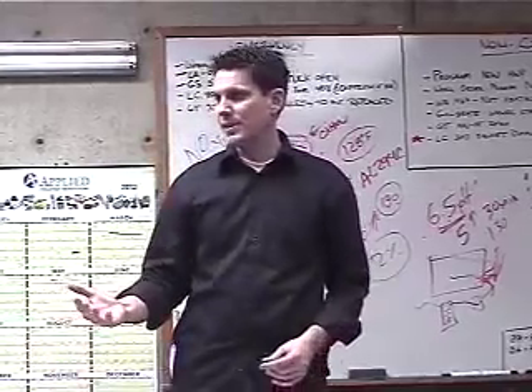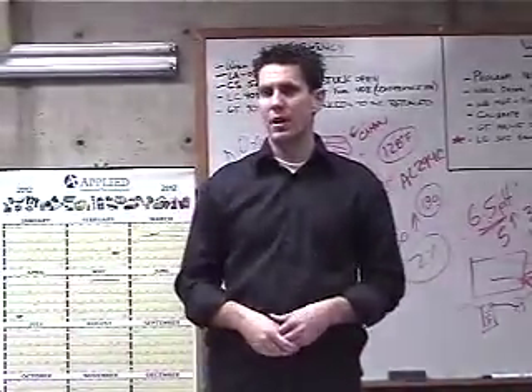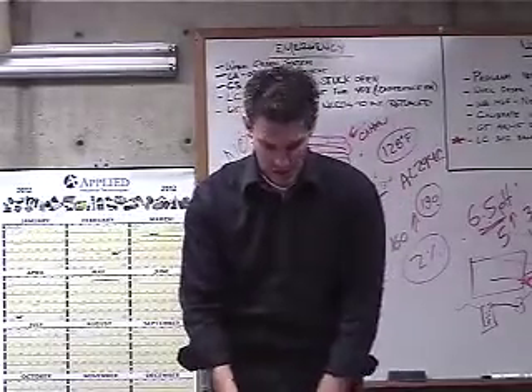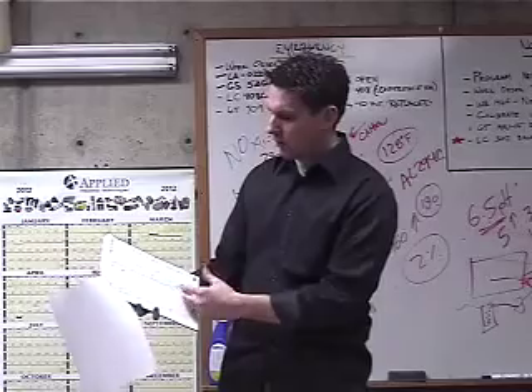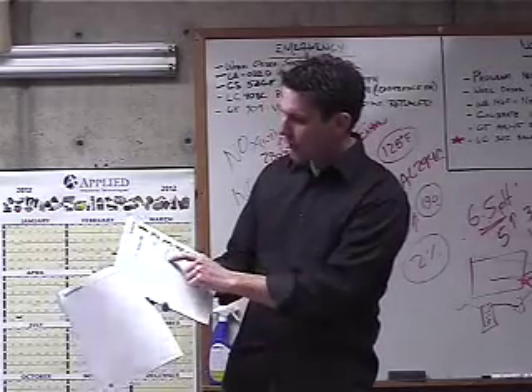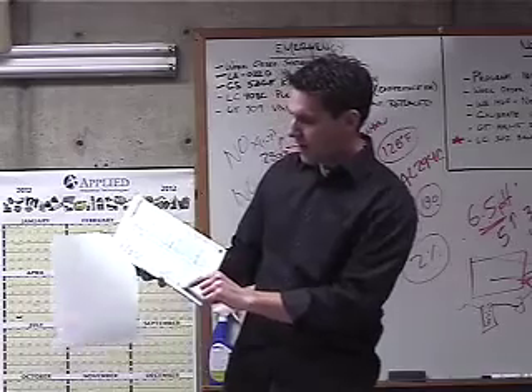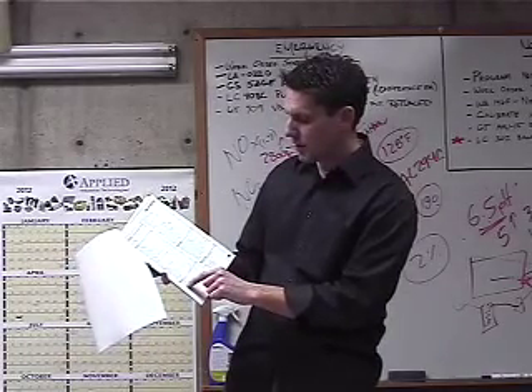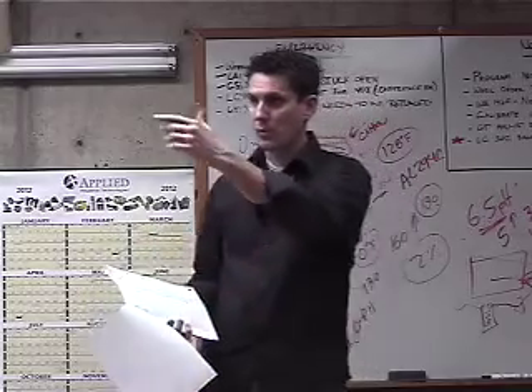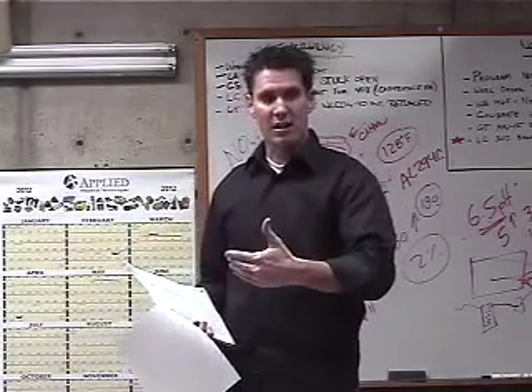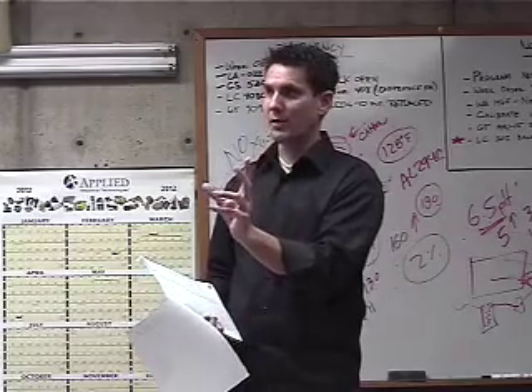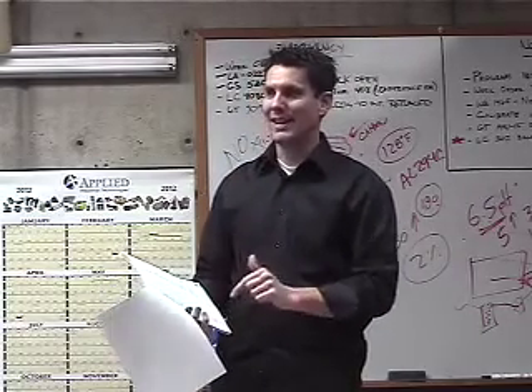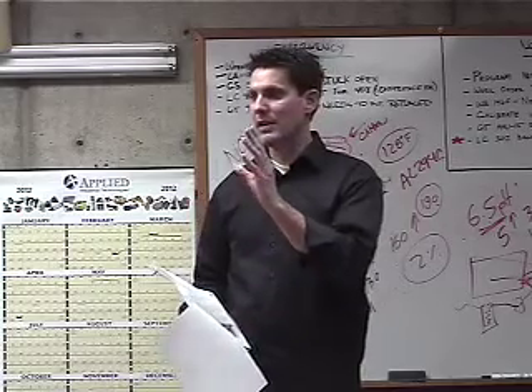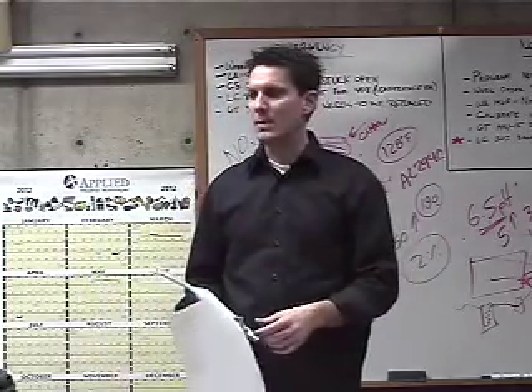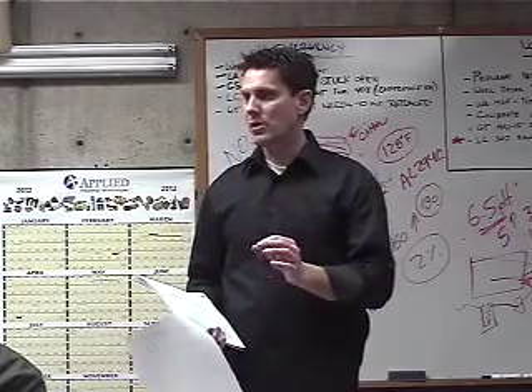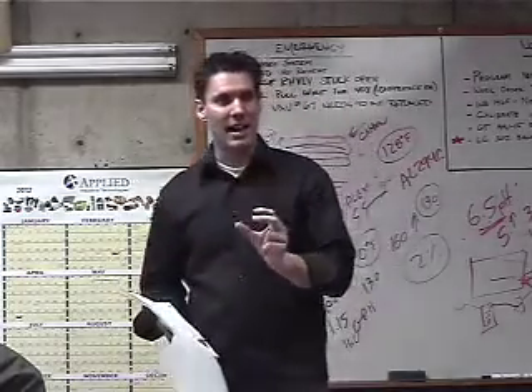I'm not going to take you through all of the startup procedures on what we do to start it up. Again, it's all detailed inside this book. You open up the book, and in the operation section they've got a pre-startup inspection and then commissioning the boiler. Commissioning of the boiler is what we do when we start the boiler up, so that we fine-tune that combustion and get it to its peak performance level. You guys should be doing that at least once a year. These things are not like an old school boiler that's operating at 80% efficiency or less. You've got to make sure that that combustion rate we just talked about is maintained, and you have to check that once a year.